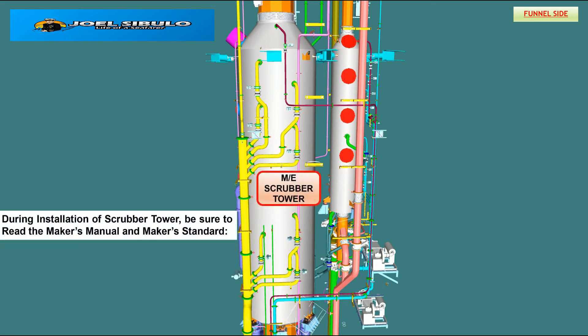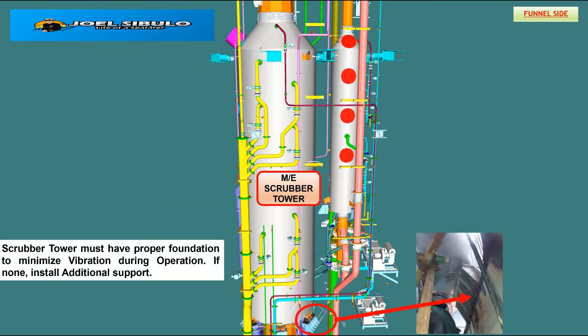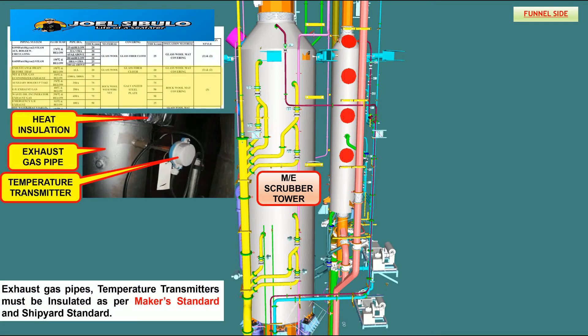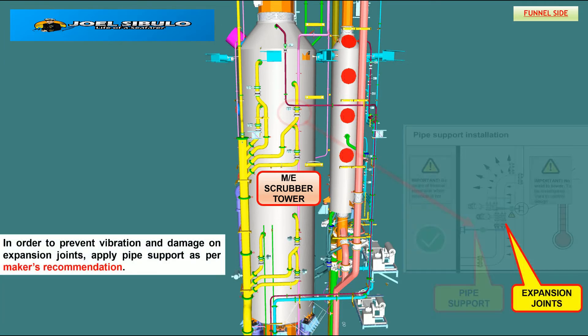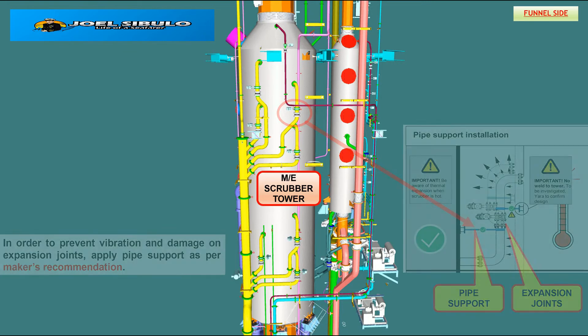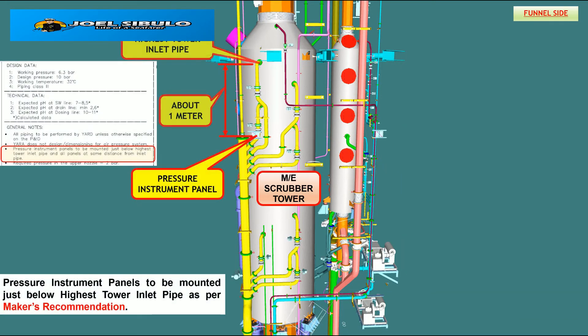During the installation of the scrubber, be sure to read the maker's manual and maker's standard. The scrubber tower must have proper support conditions to minimize vibration during operation; if none, install additional support. In order to prevent vibration and damage on the expansion joint, apply pipe support as per maker's recommendation, and mount the instrument panel just below the highest tower inlet pipe as per maker's recommendations.